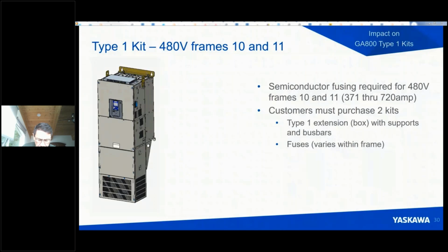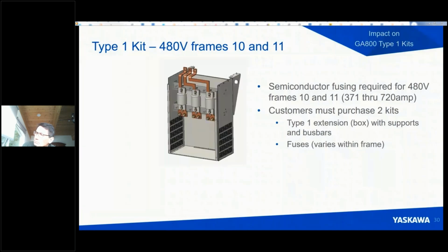since the only thing that really can protect that drive in a standalone type of situation is the semiconductor fuses, we have made a special kit, a special Type 1 kit that actually is large enough to house semiconductor fuses. Okay, this is the only Type 1 kit that's available for these two frames of the 480 volt. And internally, it looks like this. It consists of the Type 1 sheet metal itself, plus some supports and bus bar for the fusing.